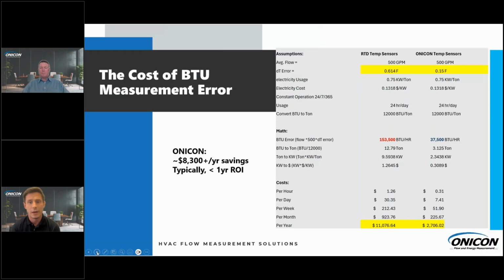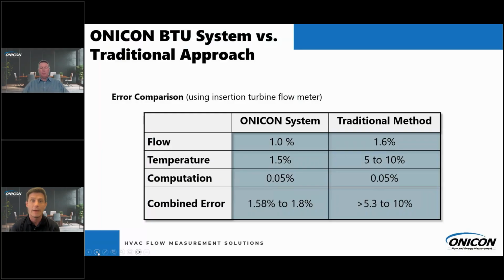Now, when you look at the BTU error, when you do the math behind the temperature sensor and that chiller efficiency, you can see how the RTD temperature sensors are off by more than 153,000 BTUs per hour compared to ours, 37,500. When you look at that annually, you can see the cost difference. It's an over $11,000 error for the RTDs, when it's just over $2,700 with ONICON. So when you compare the two, it's over $8,300 difference annually, which is typically almost an instant payback, a payback of 1 year or less. So on both sides, the tenant is getting billed for what they're using, and the supplier is billing for what they're actually supplying and what their tenant is using.